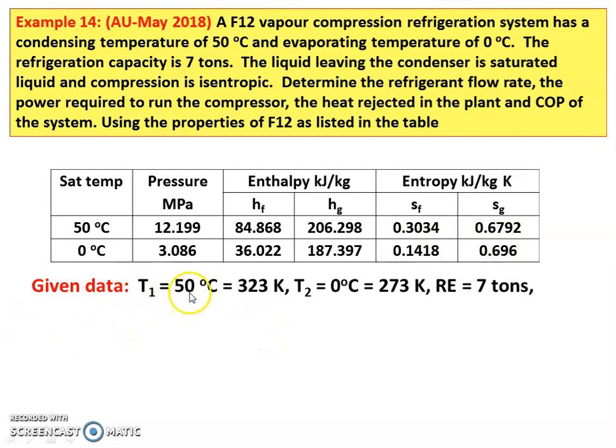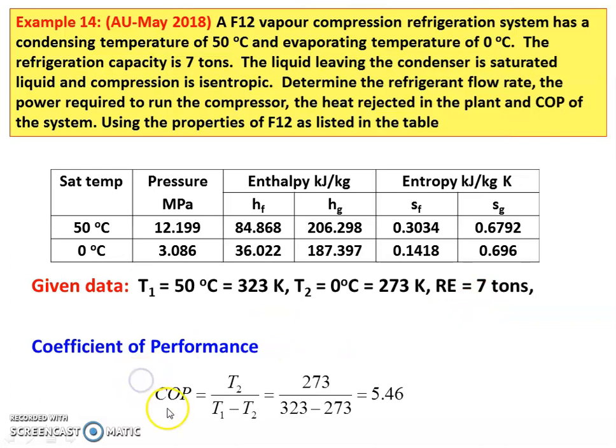Given data: T1 equals 50 degree Celsius, the condensing temperature, which is 323 Kelvin. T2 equals 0 degree Celsius, the evaporating temperature, which is 273 Kelvin. Refrigeration effect equals 7 tons. COP equals T2 divided by T1 minus T2: 273 divided by (323 minus 273) equals 5.46.